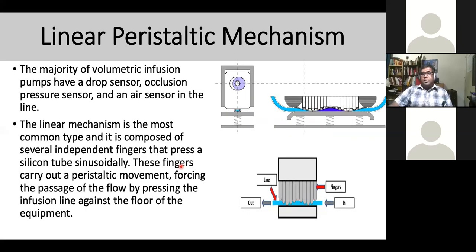More detail on linear peristaltic mechanism. Majority of volumetric infusion pumps have a drop sensor, all this, occlusion pressure, and air sensor in the line to monitor the fluid movement in the mechanism itself. So anything goes wrong, this particular sensor will indicate all the issues like pressure or occlusion, anything. Most common type used in volumetric infusion devices. This is one of the most commonly used actually.